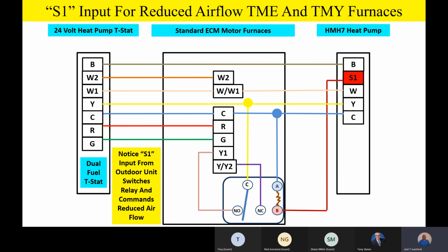And so the outdoor unit actually wires electrically like a single stage unit with just a Y input. And then we have that S1 output. So when you take a look at that, that's pretty unique to have all that functionality with just the simple 5 wires going outside. Any questions or comments on our low voltage wiring on our products that we've talked about so far before we get into variable speed air handler and a variable speed furnace? And we're also going to have a little session, talk a little bit about some airflow considerations as we start winding down our training. But any questions or comments so far on our low voltage wiring and the application of that relay?